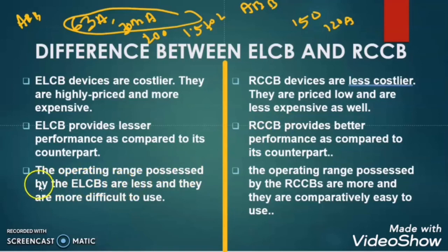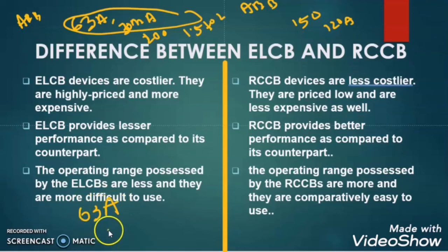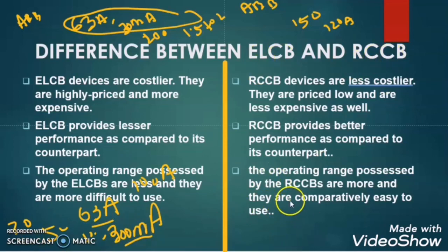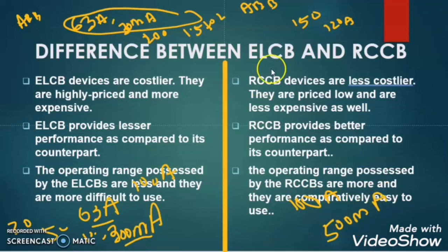The operating range of ELCB is less, while the operating range of RCCB is greater. The ELCB is commonly found up to a maximum of 63A and 300mA sensitive range, with very few at 100A. The RCCB is easily found up to 100A and up to 500mA. So the RCCB has a greater range of operation than the ELCB.